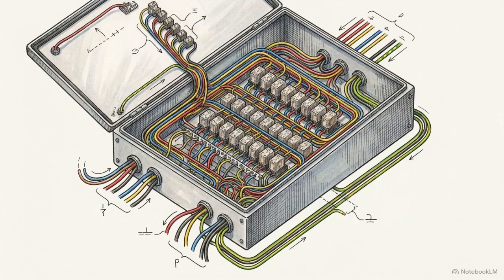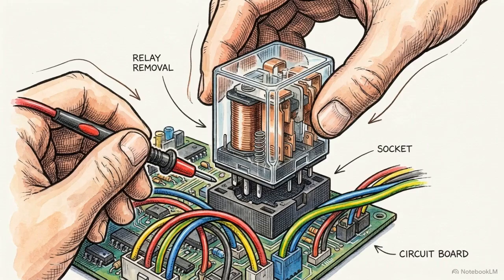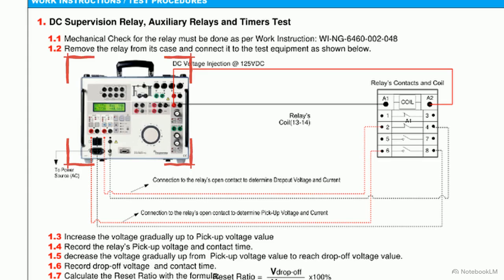The commissioning sequence now shifts focus to the ACDB's control logic and alarm matrices. First, safely isolate the target relay from the rest of the board. This prevents the test from sending unintended trip commands across the live grid. Using a secondary injection kit, engineers supply direct current into the relay coil. They gradually increase voltage to find the exact pickup threshold and operating time, then gradually decrease it to identify the precise drop-off threshold and reset time.